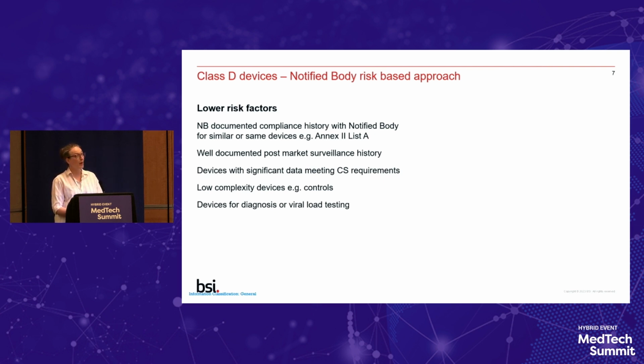A well-documented post-market surveillance history helps. So if a manufacturer comes from a self-declared IVDD, but they've got fantastic PMS records that they can show to us and show that the device has performed well on the market over time, then that again reduces the risk. Significant data meeting common specifications, low complexity devices, so many devices can just be controls with an assigned value. They're much less complex than a diagnostic device or a screening device. And devices for diagnosing or viral load testing are less risky than devices that are for primary blood screening.